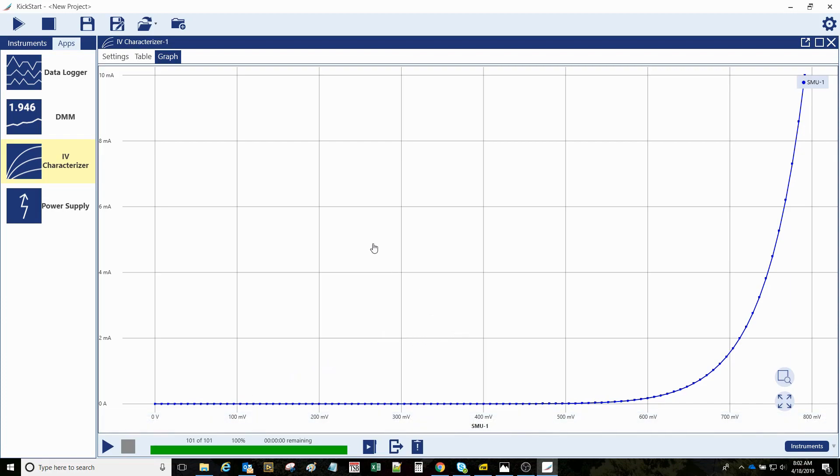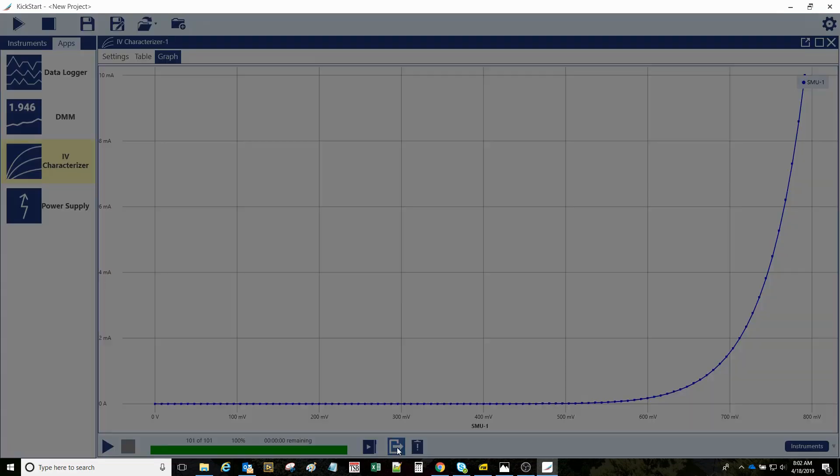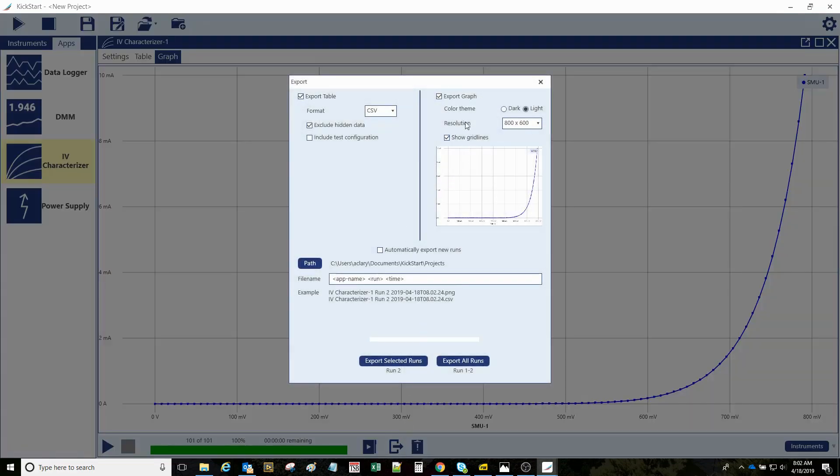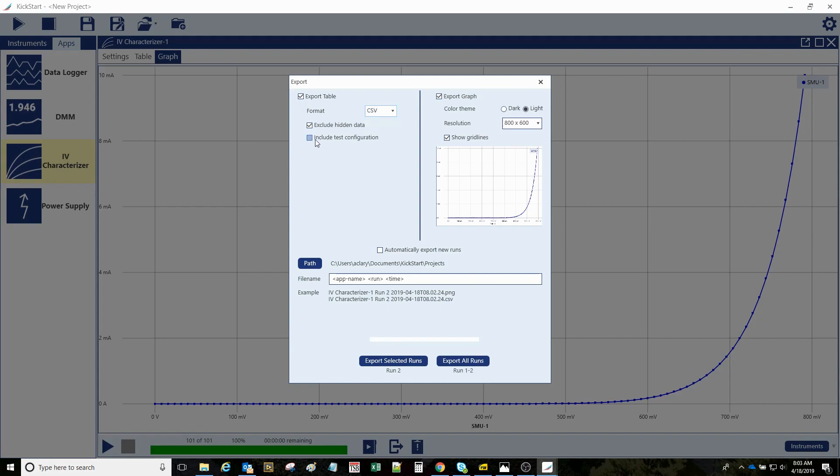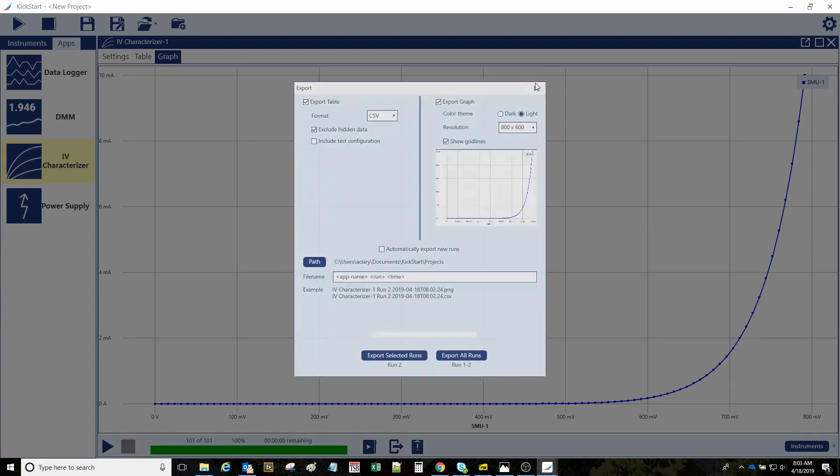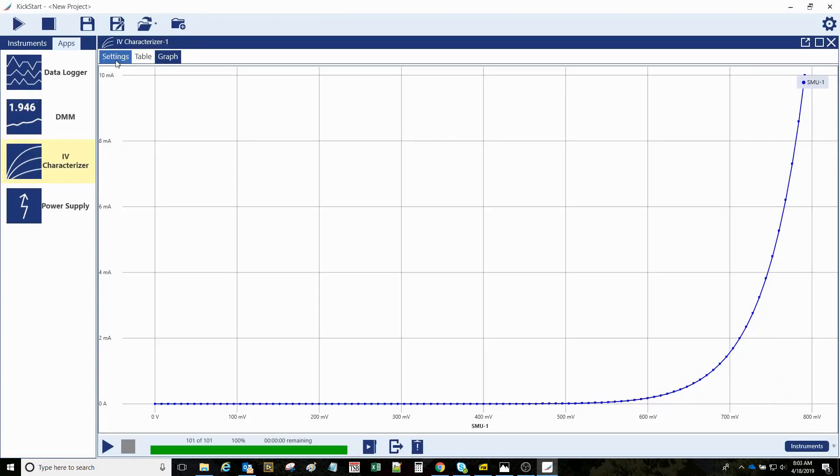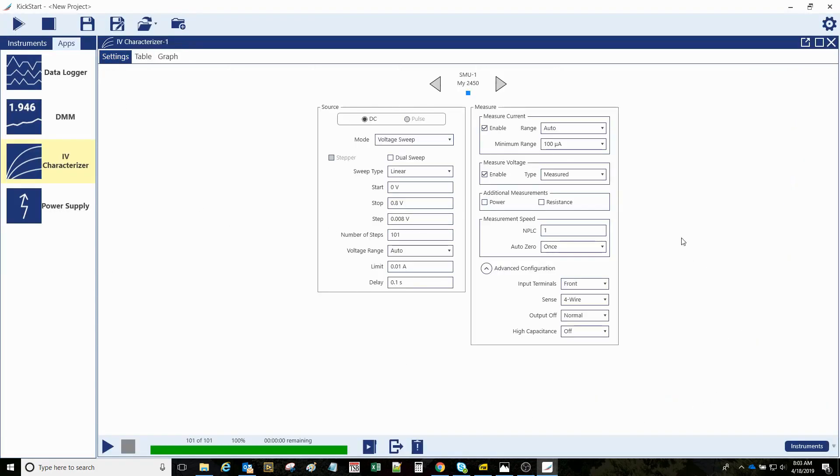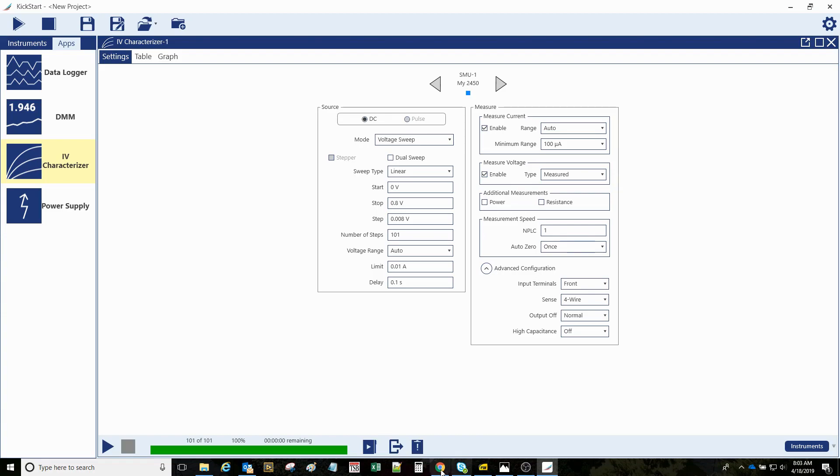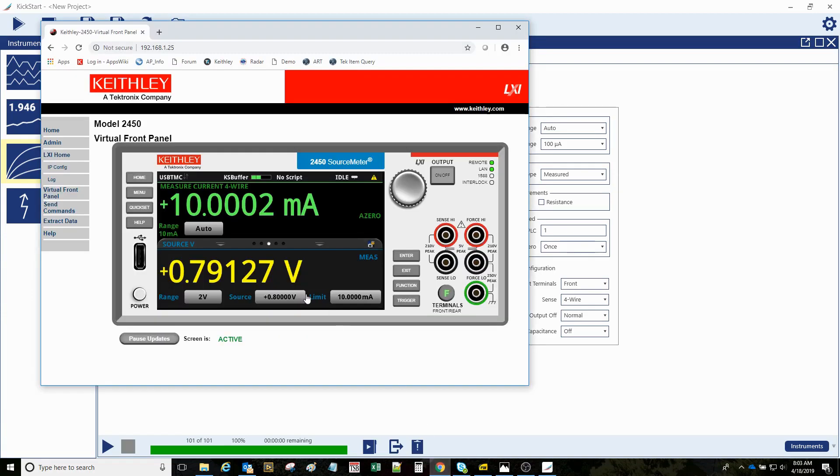All right, so data can be exported. We can export our graph. You can export the data itself in CSV or XLS. You can optionally include the test configuration, which would be the information that you've indicated here on the setup settings screen.